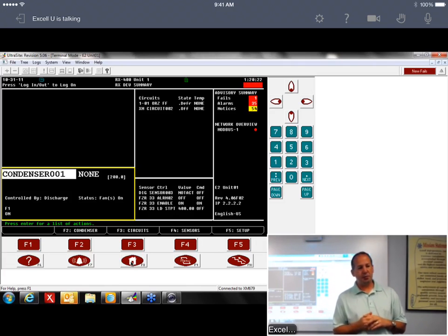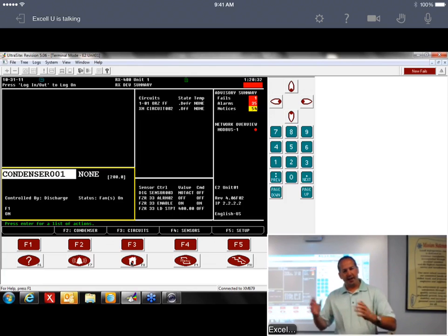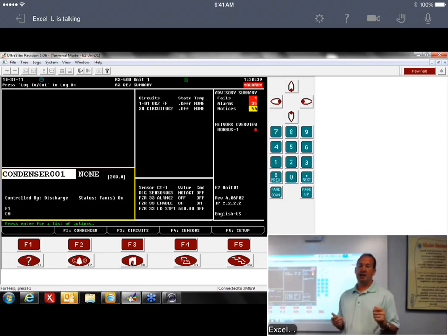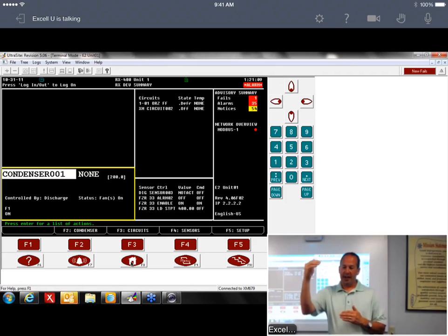Now, when it reaches the case temperature set point, then it goes to controlling superheat. So it's all right, my temperature is where it needs to be, now I'm going to control my superheat. So it kind of switches back and forth. Now what can happen in that scenario is if your valve's oversized and you meet your temperature set point, then it goes to superheat and it says, well, my superheat's too high, so I'm going to open the valve all the way up to get my superheat down. And what happens is your temperature drops. So then it says, well, my temperature's out of range, now I'm going to close the valve. And if you look at a graph of your valve percentage, you're going 0 to 100, 0 to 100. My 0 is when my case is at temperature or below temperature. The 100 is when I'm saying my superheat's high, I'm trying to bring it down, and it just keeps bouncing back and forth. So that's usually a telltale sign your valve's oversized.